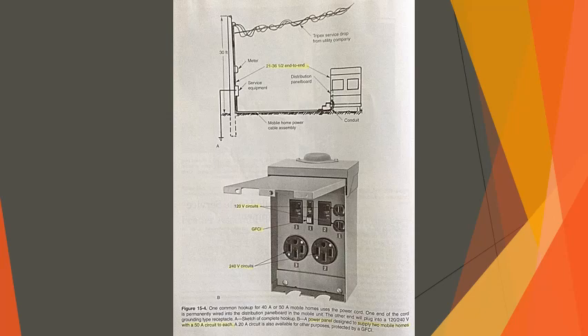This is Figure 15-4. One common hookup for a 40 or 50 amp mobile home uses the power cord. One end of the cord is permanently wired to the distribution panel board in the mobile unit. The other end will plug into a 120/240 volt, 50 amp circuit. A 20 amp circuit is also available for other purposes, protected by GFCI.